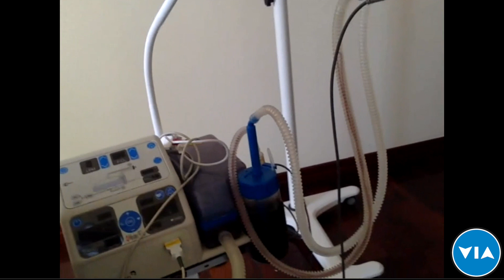The good thing about the device is that it's really durable. There's not that much to break. There are no moving elements, a lot of things are stable, and there are a few elements that wear off. The warranty doesn't cover the wearable parts. For example, the patient circuit for CPAP is a wearable. It is expected to last for about 150 cycles of autoclaving, but as you can imagine, there are certain exclusions that cannot be part of the warranty service. And obviously, if the device breaks because of heavy-handed people, somebody dropped it on the first floor, then it's not included as well. Our warranty policy is clearly defined when a customer asks. But it's a standard 1-year warranty.